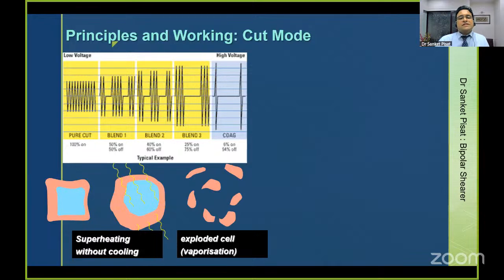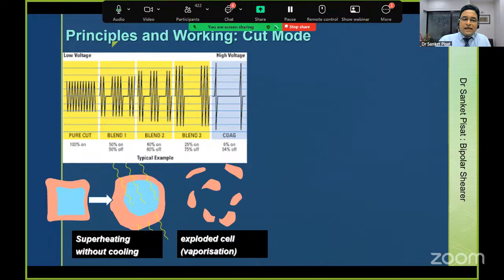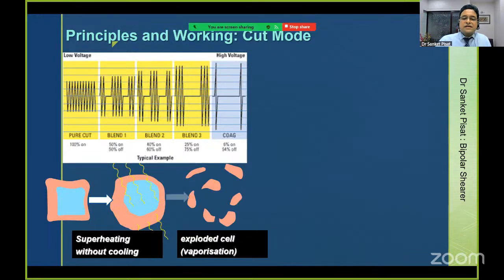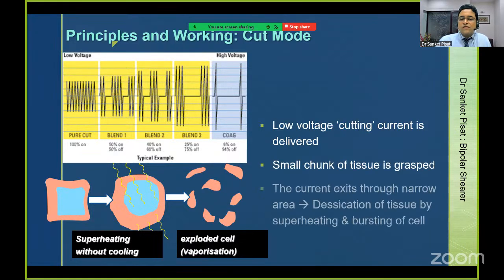In the cut mode, how does it change? This is where it gets really interesting. In the cut mode, I already explained to you the superheating concept and how the exploded cell works. So here a low voltage cutting current is delivered. A small chunk of tissue is grasped and the current exits through a narrow area, providing desiccation of tissue by superheating and bursting of the cell. This is again the same concept that we would use in monopolar, holding a very small chunk of tissue and forcing the current to exit through narrow jaws.